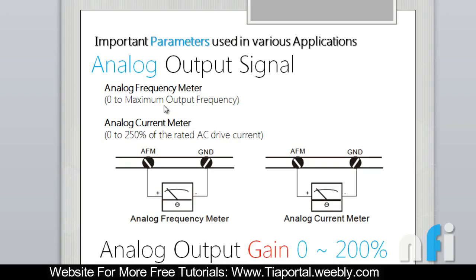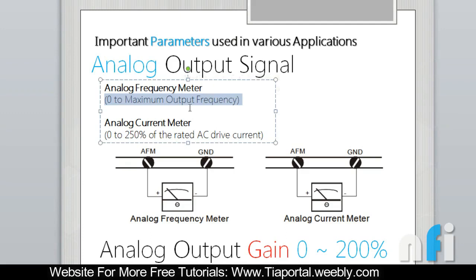This feedback is based on two things you can select. If you want feedback based on frequency, you can select the respective parameter which will give you feedback based on frequency. For example, if your frequency is 0 Hz, your feedback will be 0 volts. If the frequency is at maximum output frequency — say 50 Hz — feedback will be 10 volts. So that's the linear curve: 0 Hz = 0 volts, 50 Hz = 10 volts.